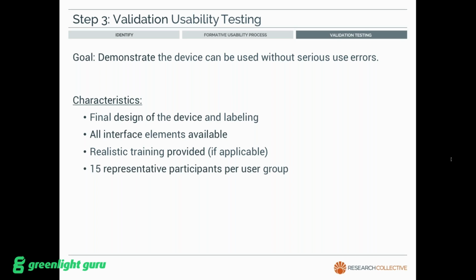In validation testing, 15 representative users is the minimum that we need to include per group. And like I said, that's the minimum. It could be more depending on the device and certain situations, but 15 is the minimum. The other important thing to note here is that's per group. So if your device has physicians, nurses, techs, all these different groups are unique, and so we need to have 15 users of each of those groups. Likewise, they would perform the tasks that are representative of their role in that procedure. So nurses will perform the nurse tasks, physicians the physician tasks, and so on.